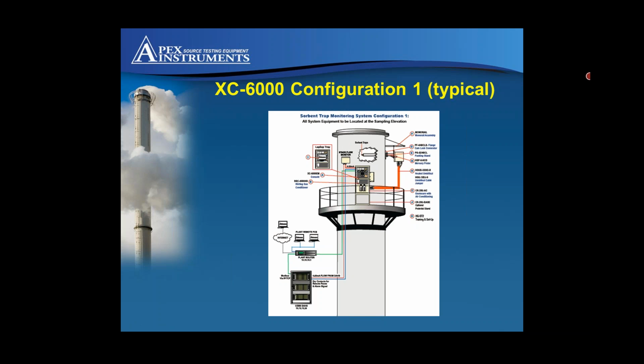I think at that elevation we've got about 7 feet in the annular space. How long is the probe? It depends on your application, but a typical probe installation will be 6 foot. You've got to extend a meter into the flow, right? Exactly, so it all depends on the thickness of walls and things like that, and your port dimensions and all that kind of thing.